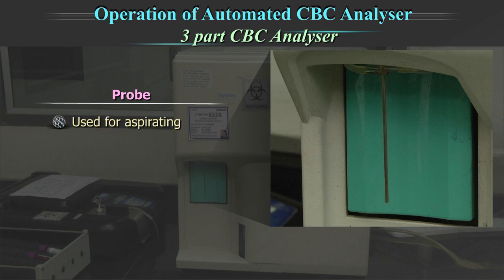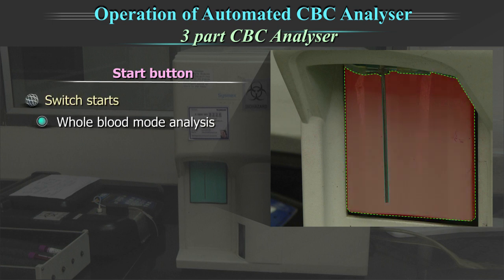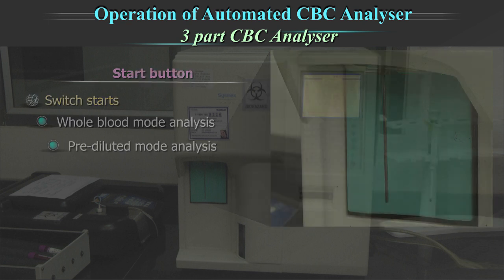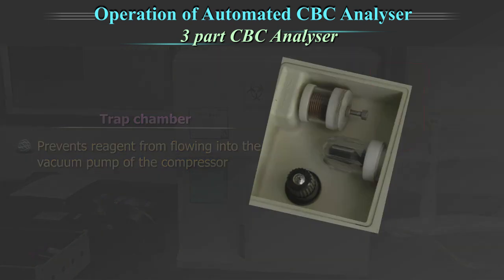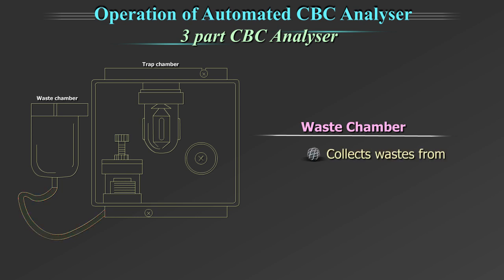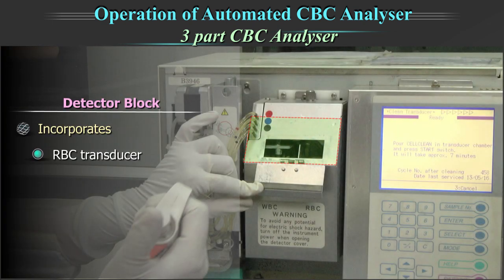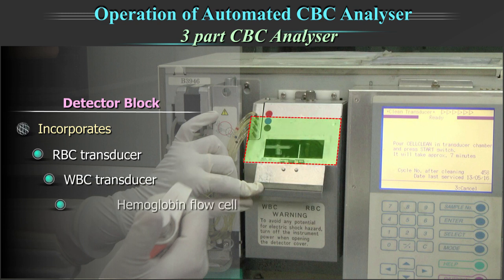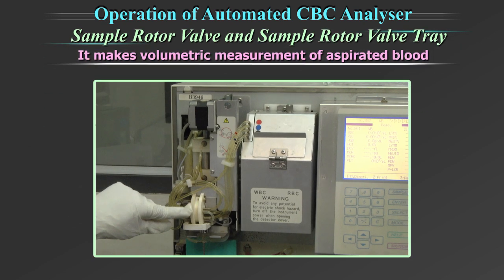The probe is used for aspirating the sample, the quality control material, or for maintenance purposes. The start button starts both the whole blood mode analysis and the pre-diluted mode analysis. The trap chamber prevents reagents from flowing into the vacuum pump of the compressor when an error occurs. The waste chamber collects waste from the transducers and mixing chambers. The detector block incorporates the RBC transducer, the WBC transducer and the hemoglobin flow cell. The sample rotor valve makes volumetric measurements of aspirated blood.